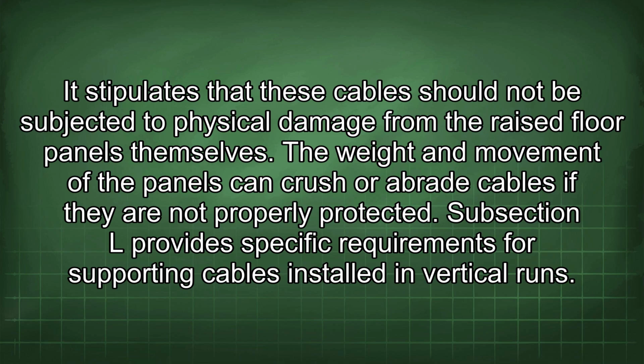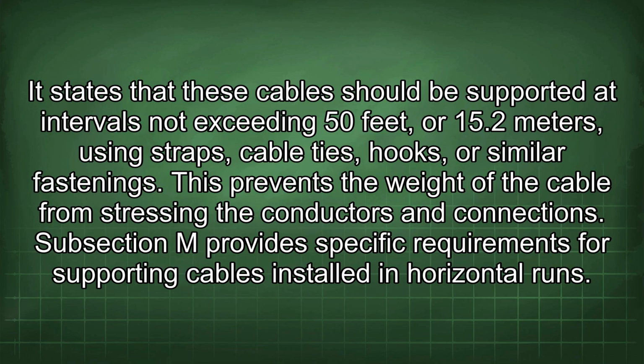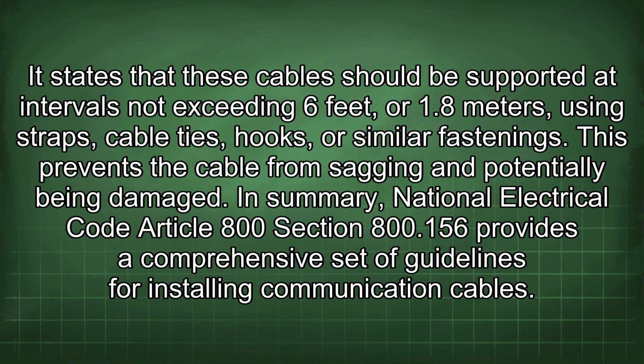Subsection L provides specific requirements for supporting cables installed in vertical runs. It states that these cables should be supported at intervals not exceeding 50 feet or 15.2 meters using straps, cable ties, hooks, or similar fastenings. This prevents the weight of the cable from stressing the conductors and connections. Subsection M provides specific requirements for supporting cables installed in horizontal runs. It states that these cables should be supported at intervals not exceeding 6 feet or 1.8 meters using straps, cable ties, hooks, or similar fastenings. This prevents the cable from sagging and potentially being damaged.